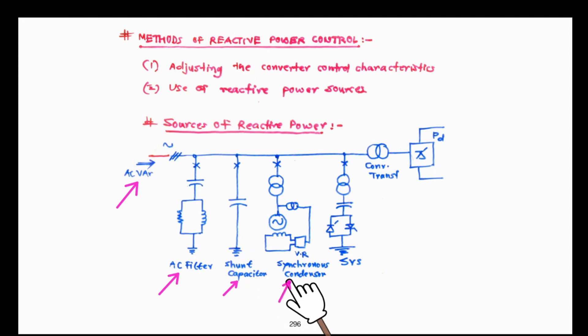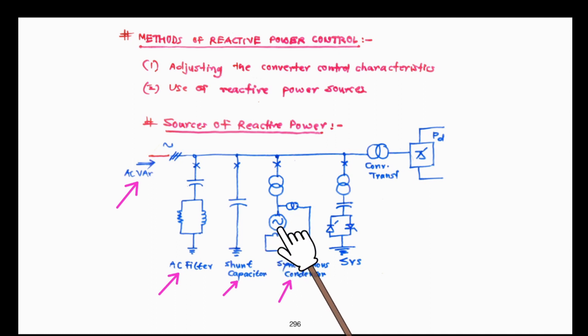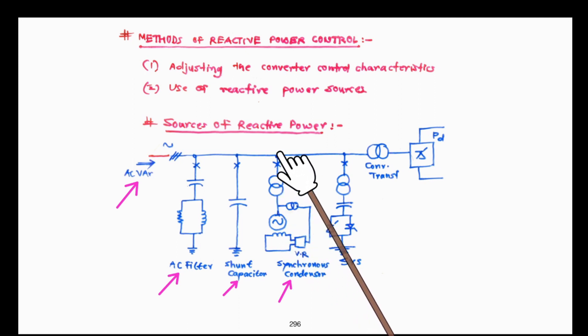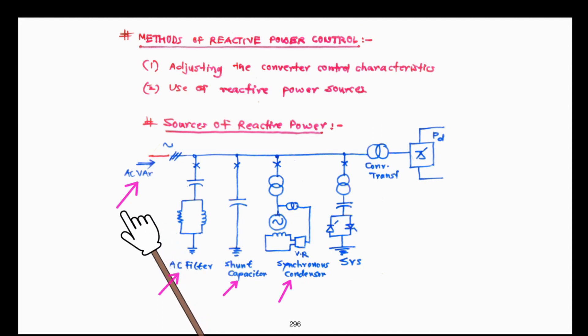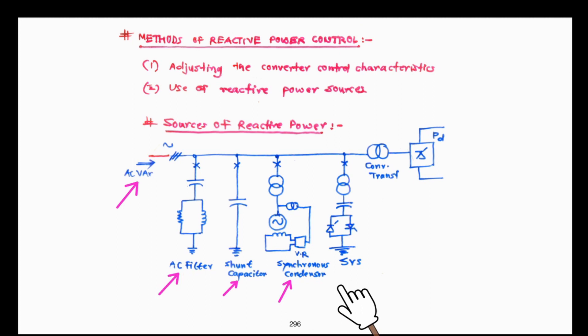The second most important element that can supply reactive power is the AC filter. AC filter design provides filtering of AC current harmonics, but the capacitor in the filter supplies reactive power for the fundamental frequency — so it serves a dual purpose. These filters are mechanically switched, meaning the capacitors are available in the form of small banks and are switched in steps, not with smooth continuous variation. They are less expensive compared to static VAR systems and synchronous condensers, which require specialized controls, electronic circuits, and coordination.